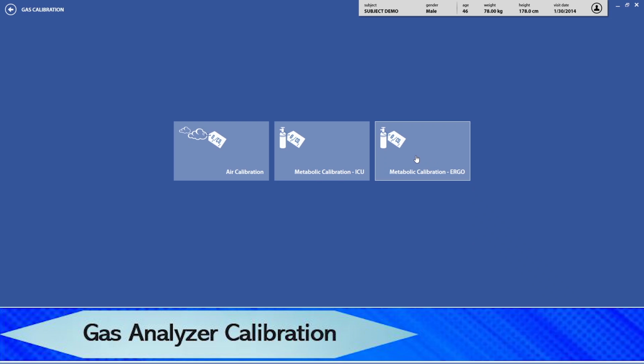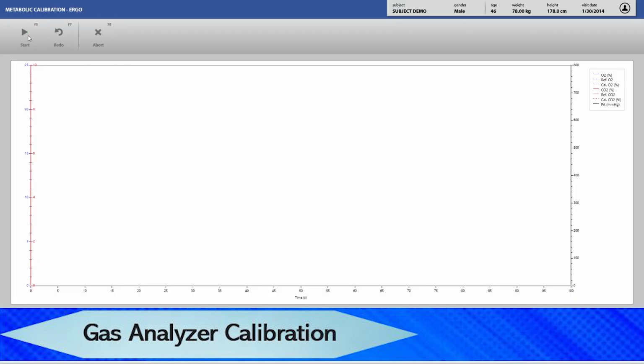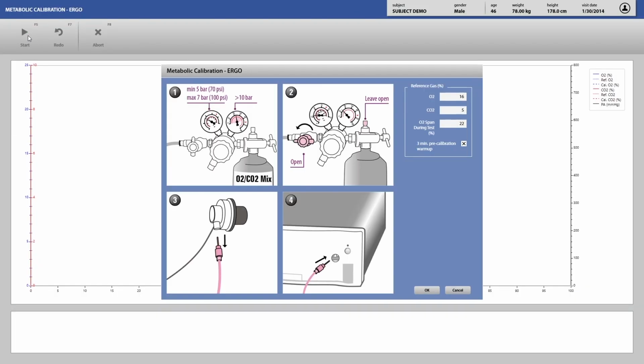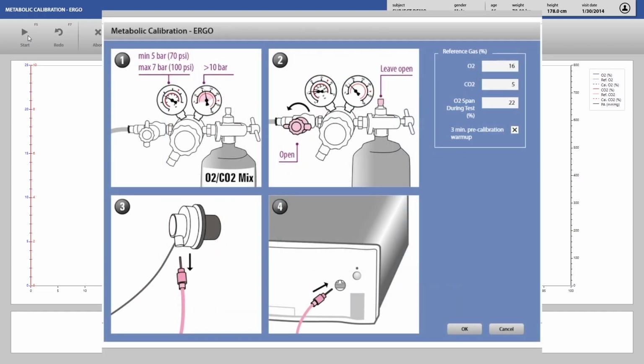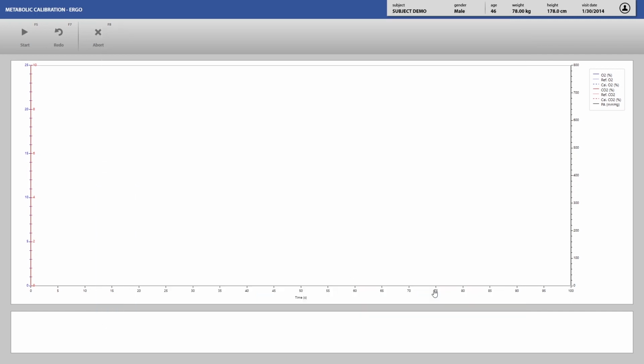Modern CPET systems contain rapid gas sensors. These rapid gas sensors can measure oxygen uptake and carbon dioxide output as frequently as breath by breath. Gas calibration is an automated process. Most CPET systems show reminder messages if calibration is yet to be done.